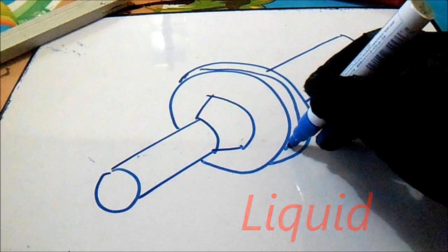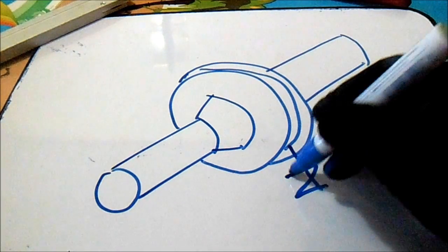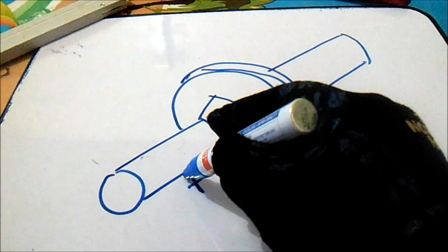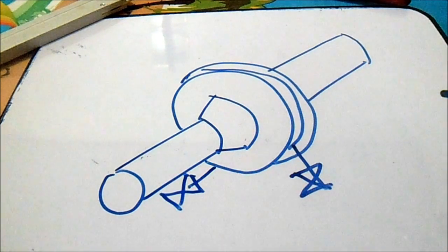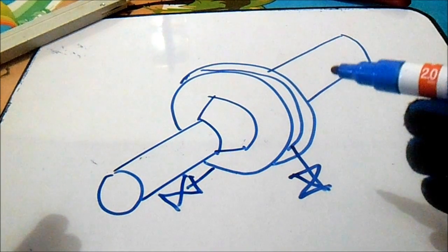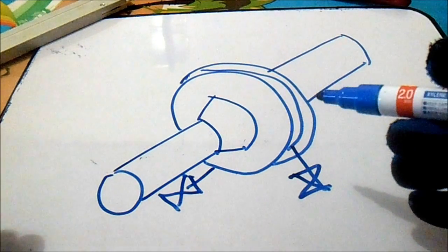So for the flow orientation of orifice flange, if the two valves are going down here and another one is here, it means this is liquid. Okay, the orientation of the valve here is for liquid. The flow direction is going there.